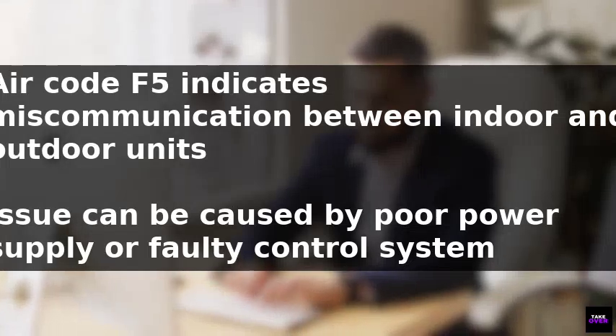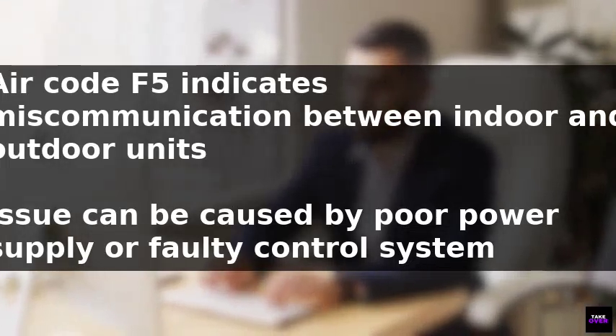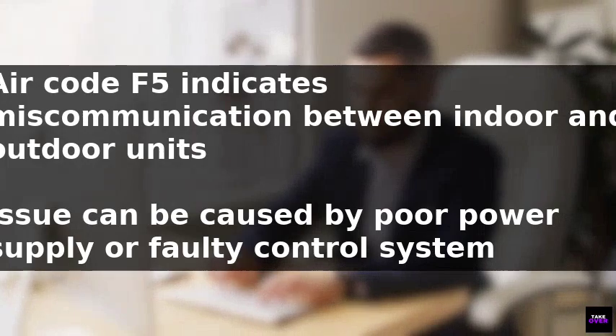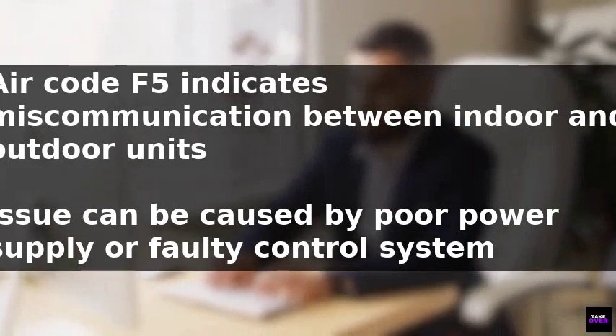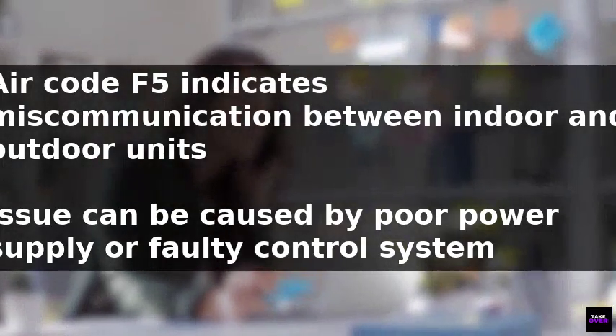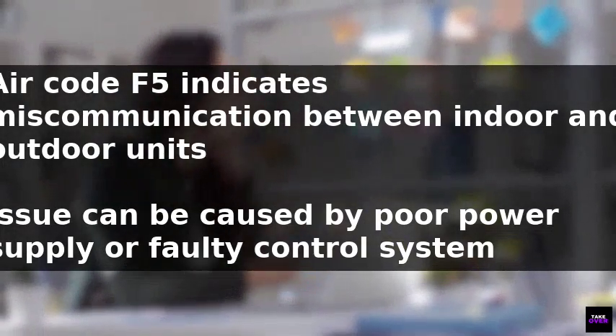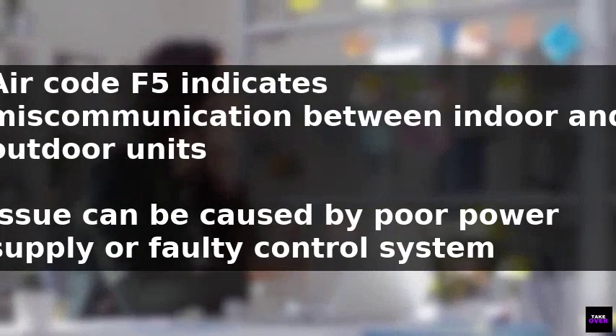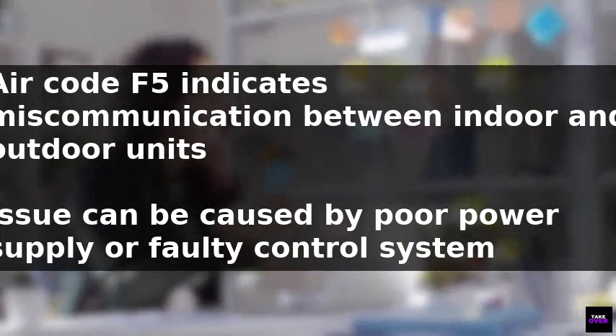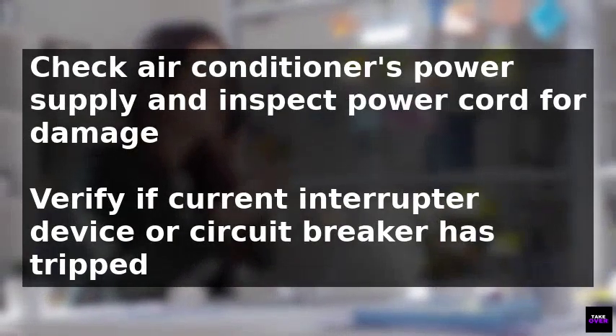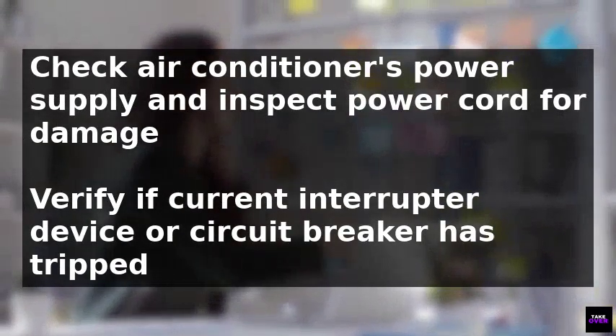An error code F5 on an air conditioner indicates a miscommunication between the indoor and outdoor units. This issue can be caused by a poor power supply, a faulty control system, or bad or damaged wiring. To resolve the problem, start by checking the air conditioner's power supply.